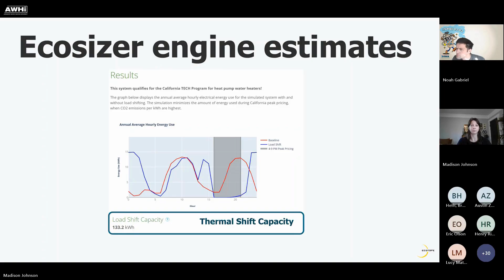The second method for estimating load shift capacity is the NEEA load shift test. This test can be completed in a day during startup, and it has been incorporated as part of Ecotope's commissioning process for these new load shift demonstration sites. Our first step is to let the heat pump water heater settle under normal operation under 0 draw conditions. So we're just going to let the heat pump charge as it would in its normal operation.